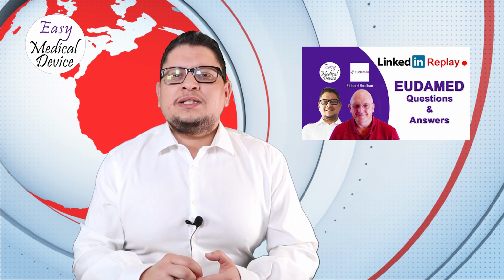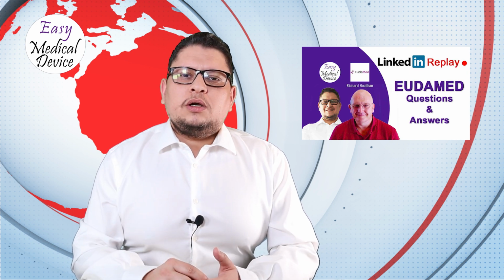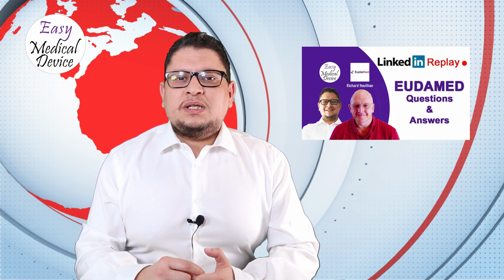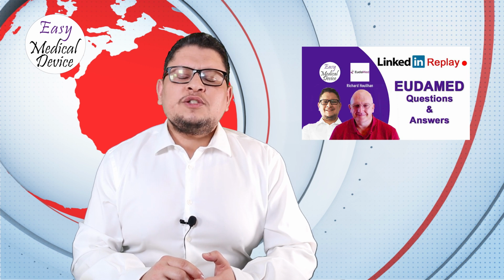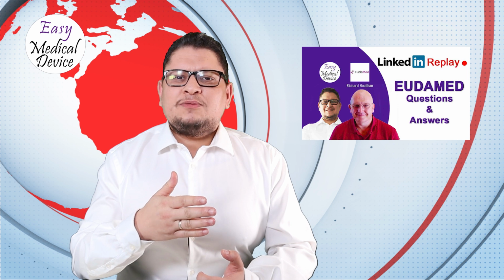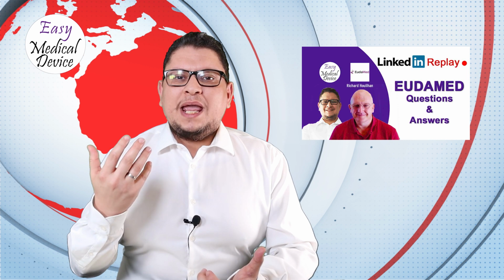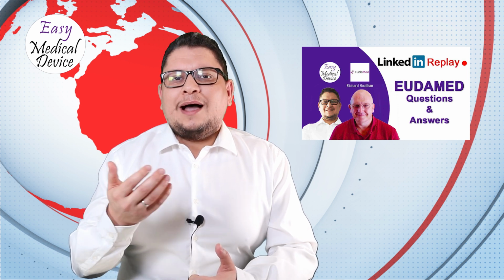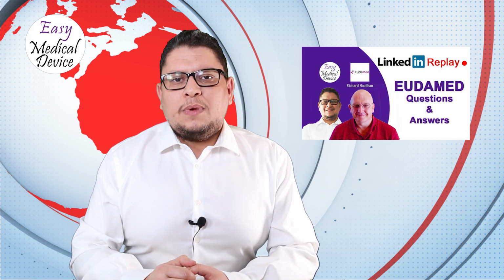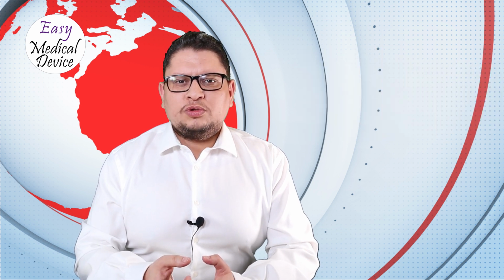Richard has also created a template that you can download for free, where you can create your own legacy device tracker, with a UDI number, because you need that in case of any vigilance reporting during this transition period, between the 26th of May 2021 and the 26th of May 2024. If you have any vigilance reporting for your MDD device, you still have to register this device on the EUDAMED database, and you also have to have a UDI number. If you don't have one, this will help you to create your UDI number.